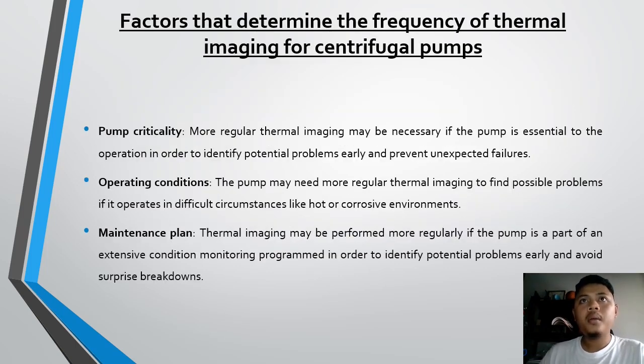Factors that determine the frequency of thermal imaging for centrifugal pumps: first, pump criticality. More regular thermal imaging may be necessary if the pump is essential to the operation, in order to identify potential problems early and prevent unexpected failure.